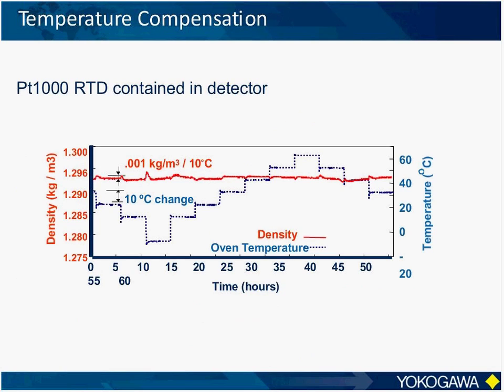Now, most vibrating element detectors have an integral temperature sensor which measures the temperature of the gas sample itself. This allows the system to measure the raw density of the gas at process temperature, but it also allows us to calculate a density value at a standard reference temperature. This is typically 0 degrees Celsius. This also means that neither the gas sample nor the detector itself has to reside in a temperature-controlled environment.